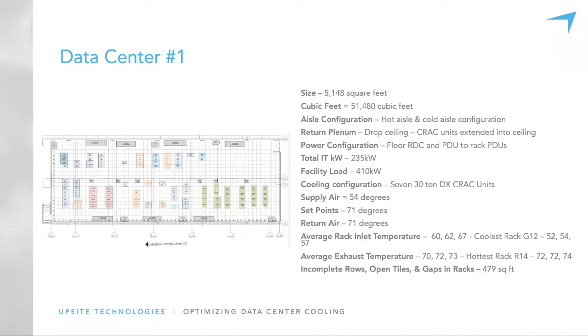I know they had 7 30-ton DX CRAC units. Supply air was coming out at 54 degrees. Their set point was 71, and their return air was 71. I'll go back to Lars and his 4 delta T's. If we look at the delta T from the front of the rack to the back of the rack, there is not really a delta T to mention. This is extremely important. DX units, they were designed to take as hot of air as possible, and the hotter that air, return air is, the more effectively it can compress and turn it into chilled air to supply the air for the racks.